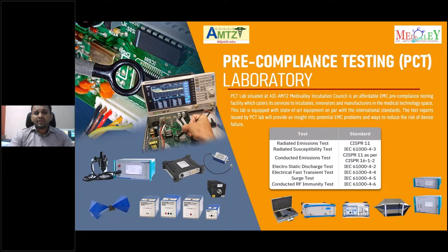And there is a full compliance lab which is set up in a PPP mode, public-private partnership, where the operation or service provider is TUV India, which is a renowned testing body. They have one of the largest EMI EMC facilities at AMTZ with a 10-meter semi-anechoic chamber, and we have an acoustic chamber too, where we can test as per IEC 60601-1-8, which is particular to the testing of medical alarms.